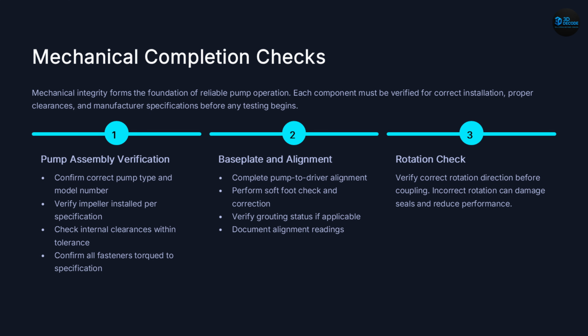Now let's move to the equipment itself, because mechanical integrity forms the foundation of successful testing. The first step is pump assembly verification. Confirm the correct pump model, correct impeller, correct internal clearances, correct fastener torque. Every detail matters. Then comes alignment. And this is where many problems begin. Pump-to-driver alignment must be complete. Soft foot must be eliminated. Alignment readings must be documented because poor alignment creates vibration, and vibration immediately creates test failures.